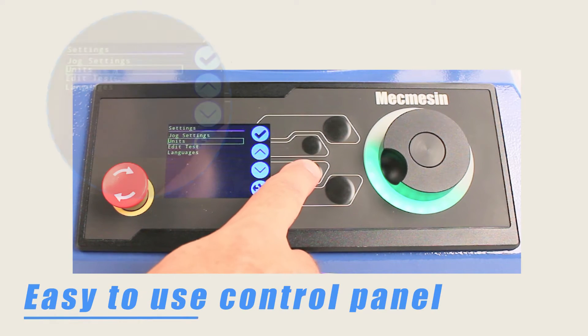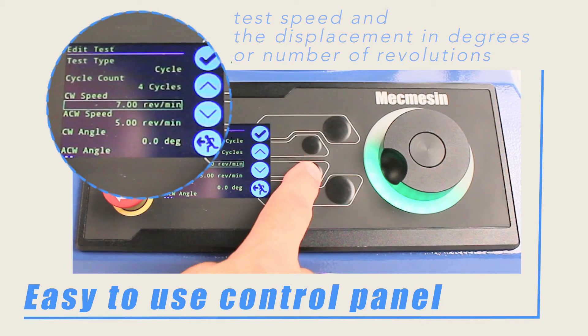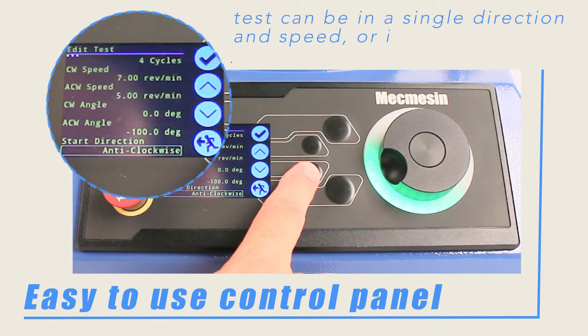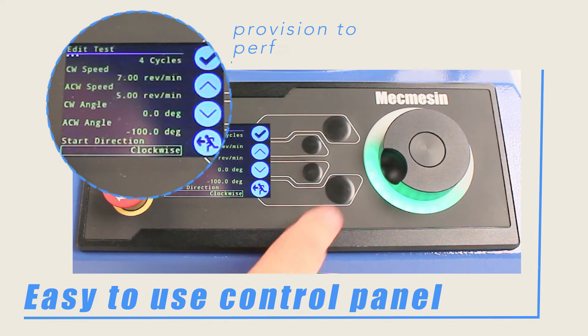The control panel can be used to set and display the test speeds and the displacement in degrees or number of revolutions with digital accuracy. The test can be in a single direction or in both directions and at different speeds. There is also the provision to perform cyclic tests.